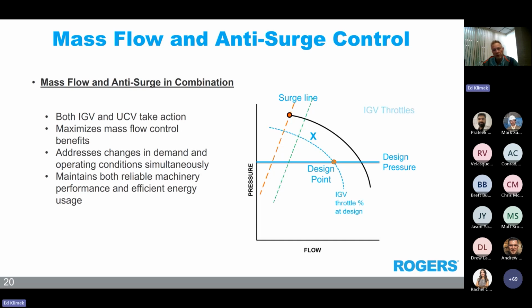Here you have the mass flow control effectively throttling the IGV position in response to the different ambient conditions, down to, you'll see the dashed line there, which is the design set point. At this point, we will still exceed the targeted discharge pressure and are approaching the surge line. The anti-surge controls can then open the unloading control valve to reduce the compressor's discharge pressure to attain the new design point. I'll run through that one more time.